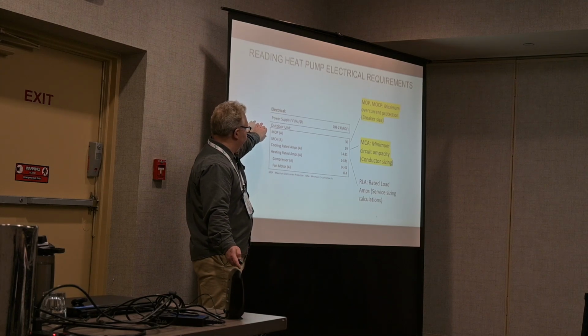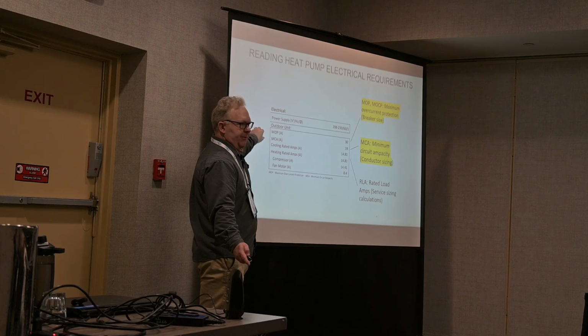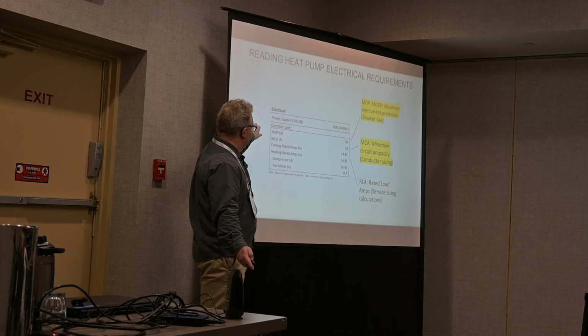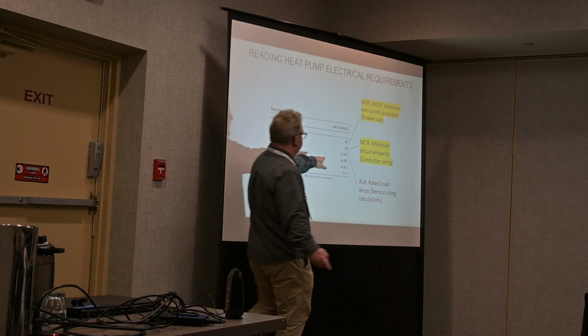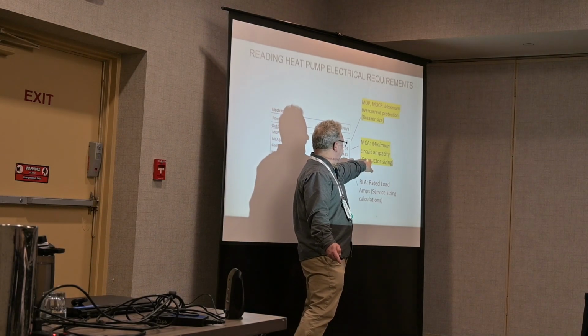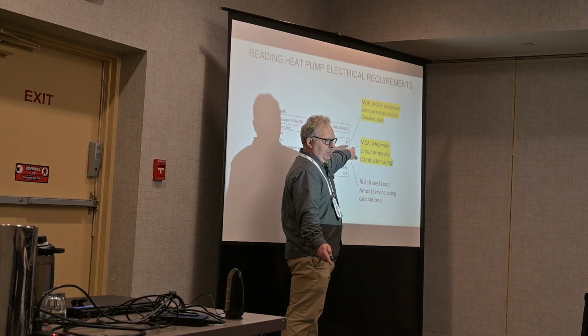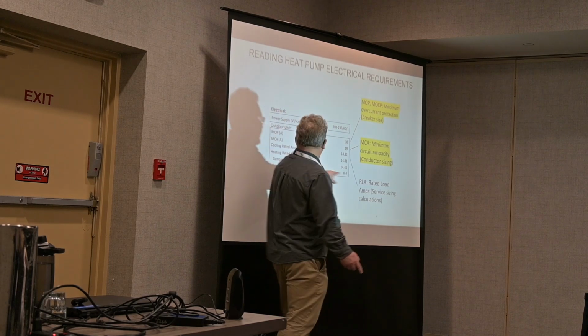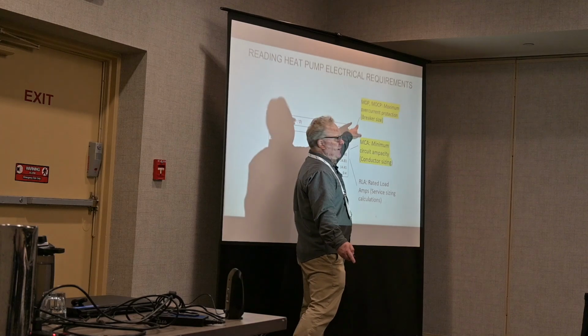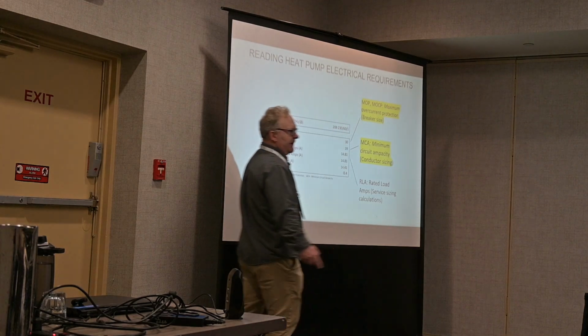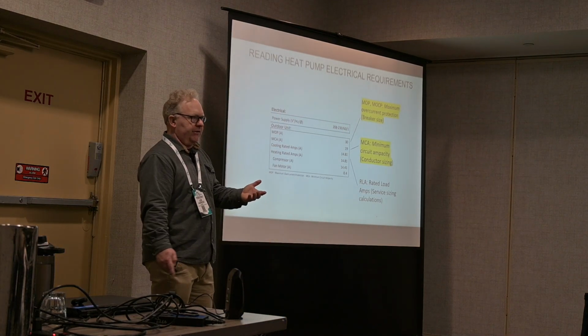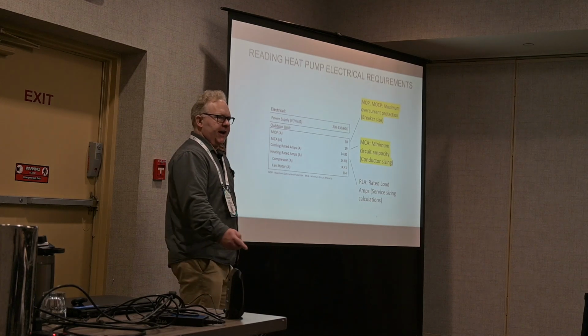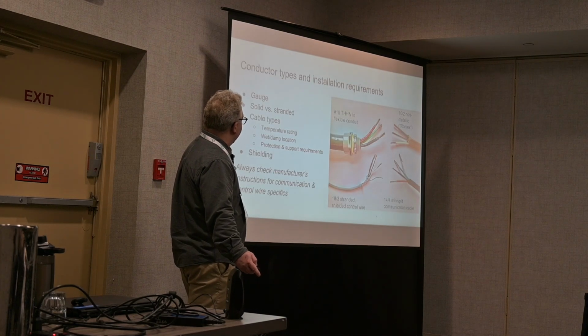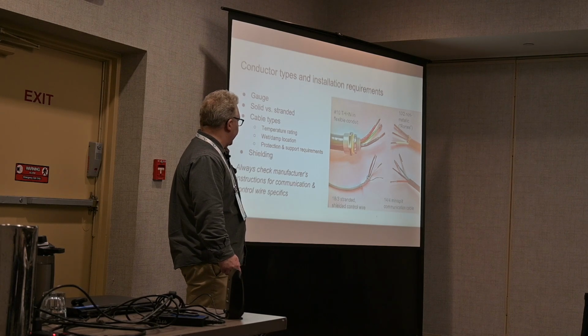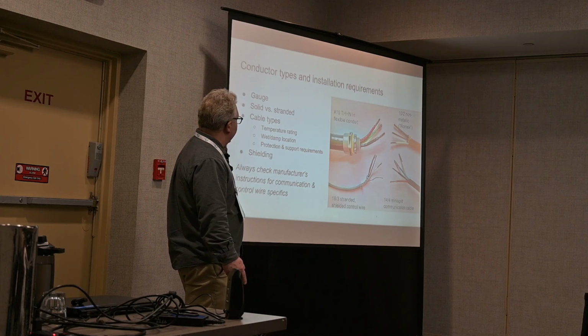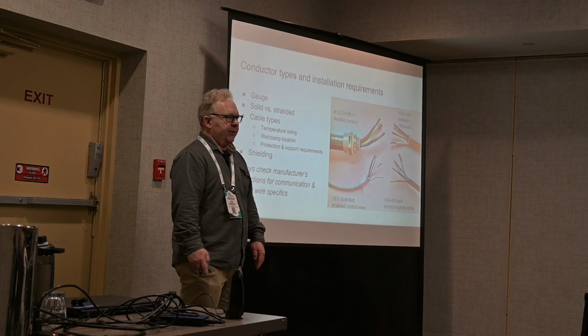These are the critical pieces of the heat pump submittal when it comes to the actual installation. The MCA, the minimum circuit ampacity, tells you the ampacity of the conductor you need to use. And the MOP tells you the breaker size. And so if you're doing QA on one of your installs, these are things that you can check. There are different types of connectors, conductors. It's good to become familiar with those.